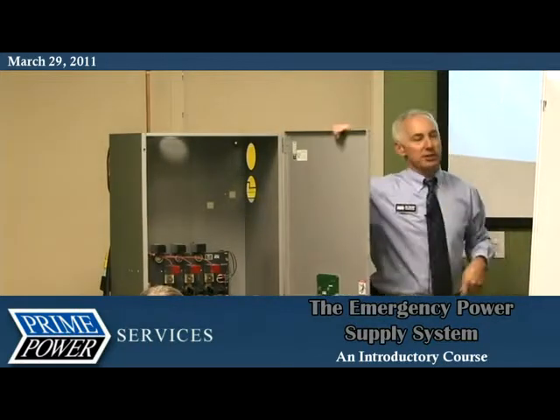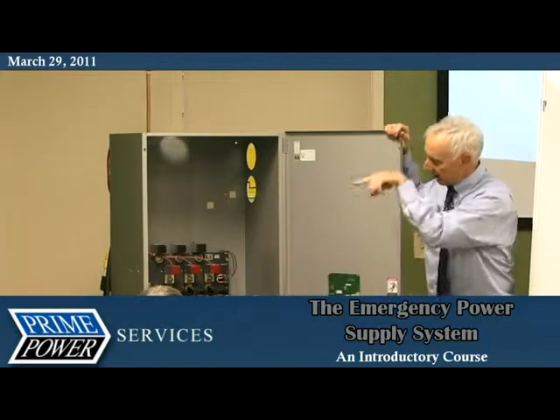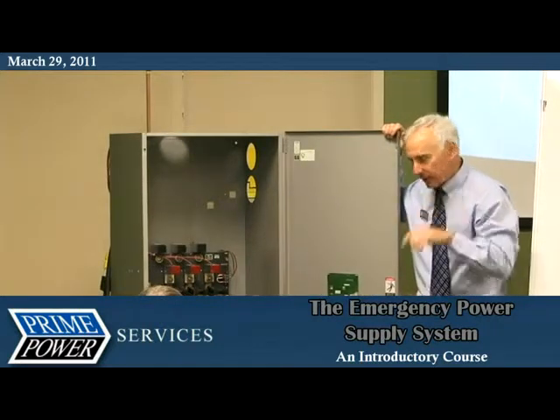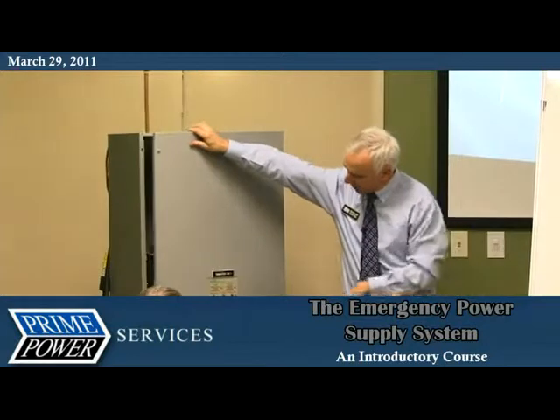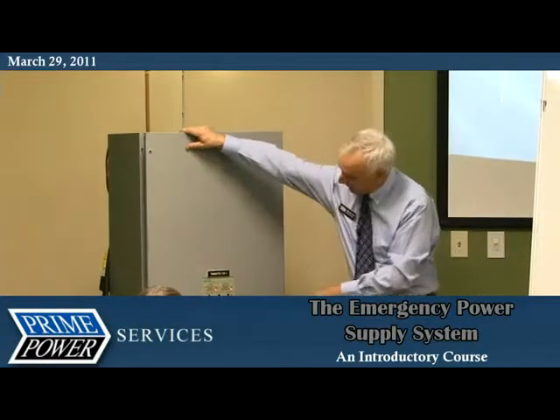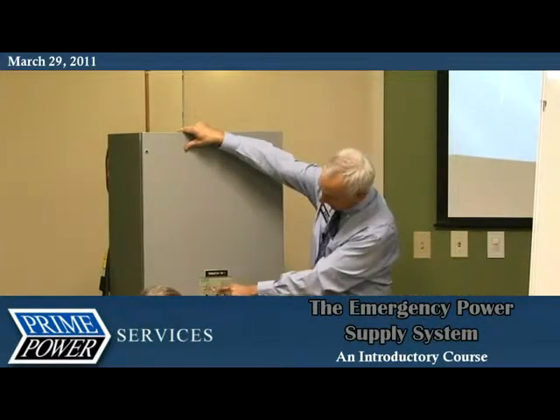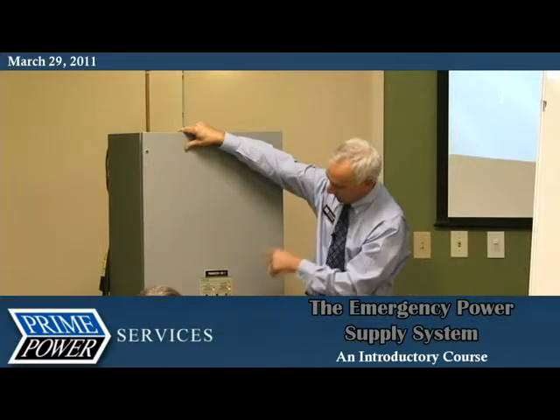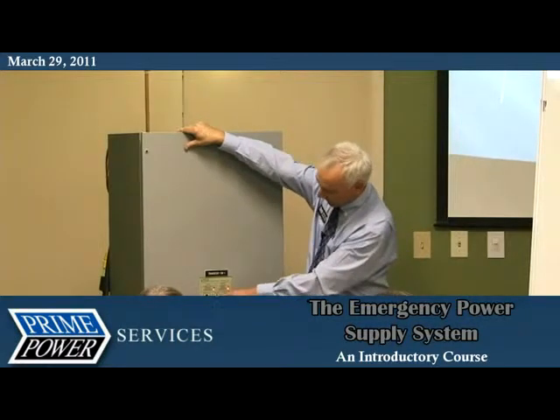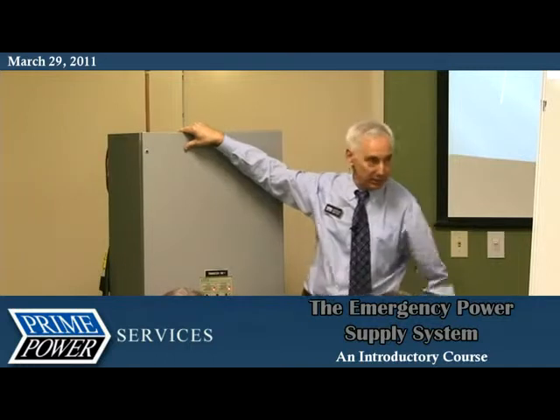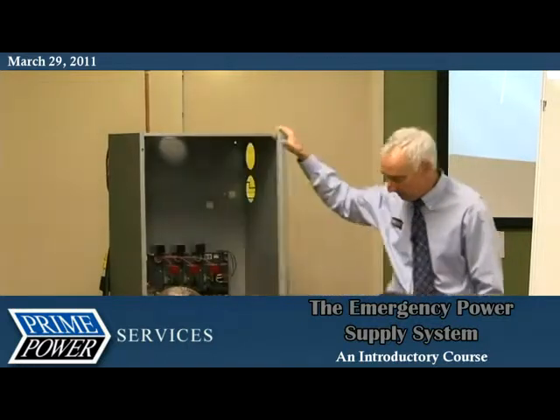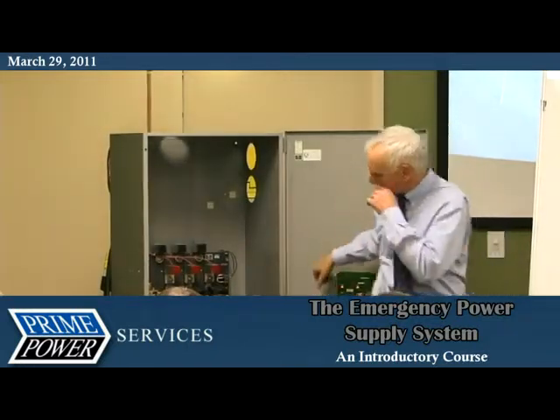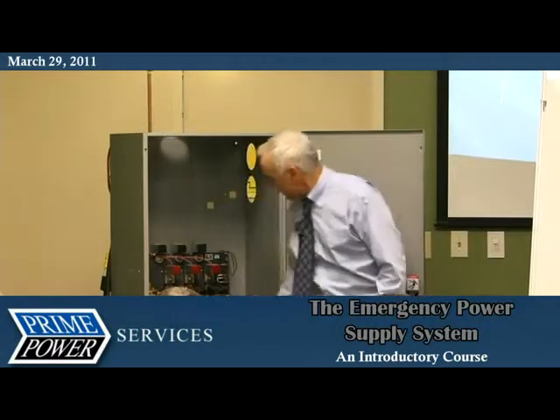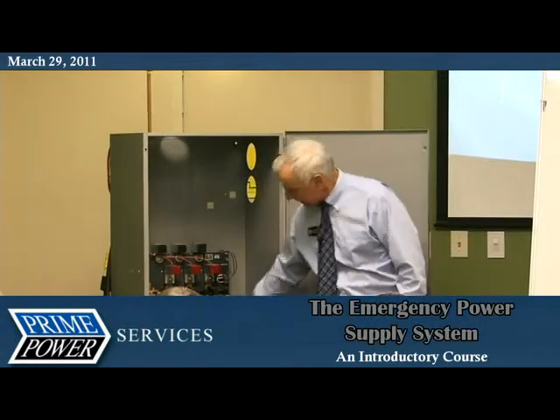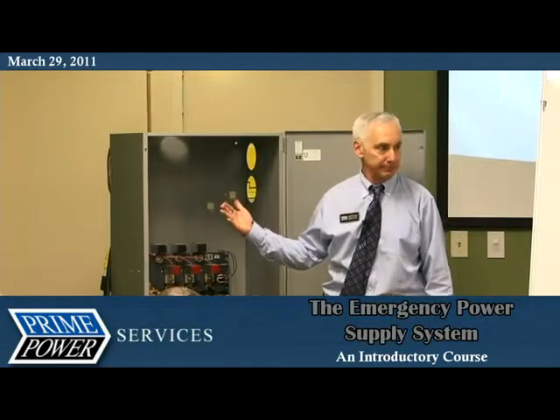It's sending a start signal right now to my generator outside. Hear a little thunder out there? Now we see the light come back on. We lost the source available on normal. We have emergency available, and we have connected to emergency. What happened inside here is now this indicator says emergency, but this set of contacts flipped up.